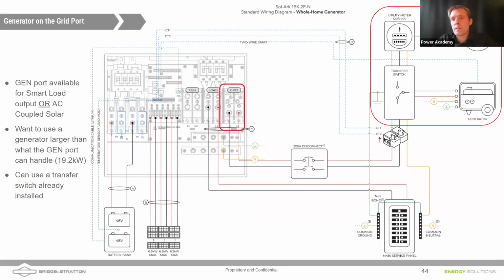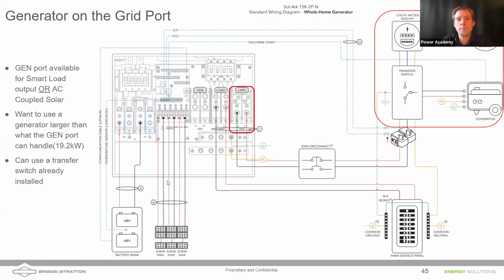Now, you might also have installations where there's already a generator on the house and there's already an automatic transfer switch. You can utilize this, and you can still utilize the two-wire signal to start, right? So we don't have to have auto main sensing enabled on the generator. We can still use a two-wire signal to start. And what's going to happen in a grid down situation is that the batteries would cover loads first. The battery output is going to support the loads until the batteries get low enough that it starts up the generator and causes the transfer switch to kick over to generator, and uses the generator to charge the batteries back up.